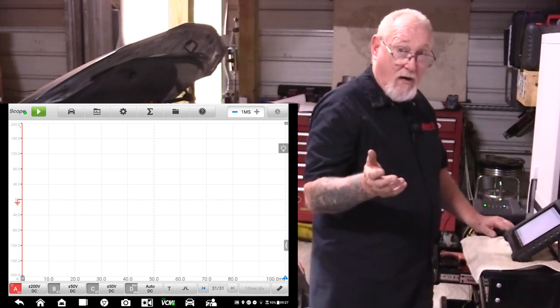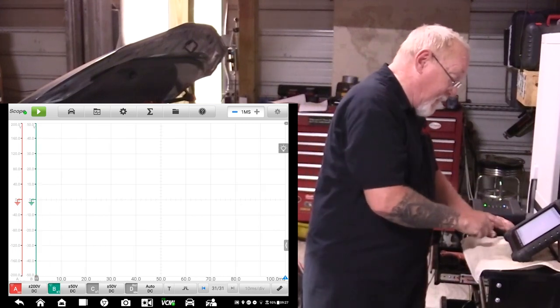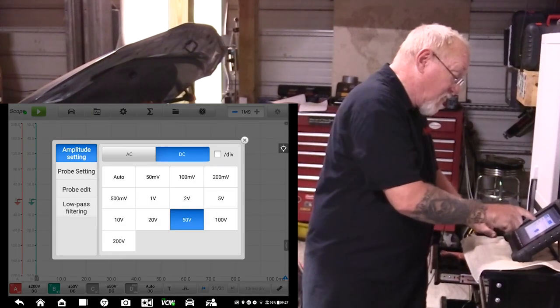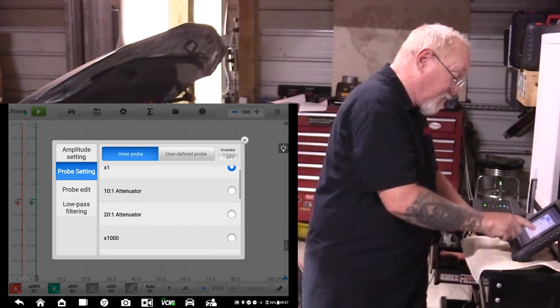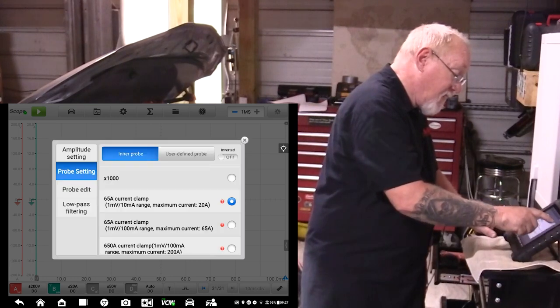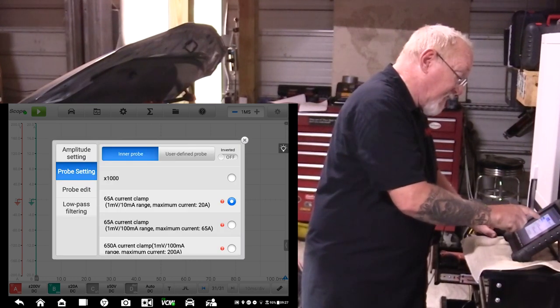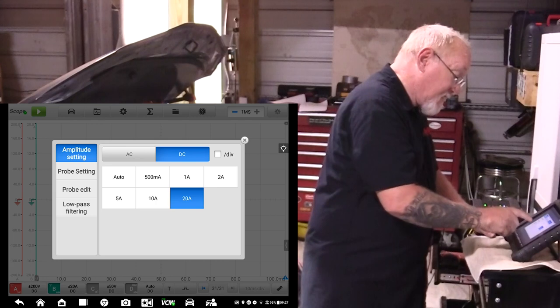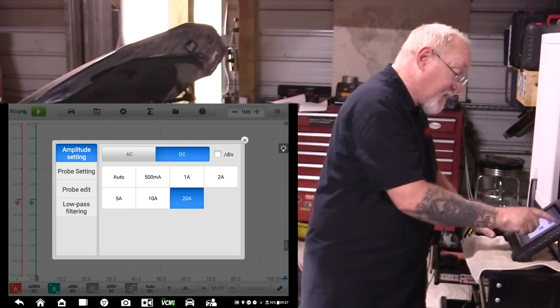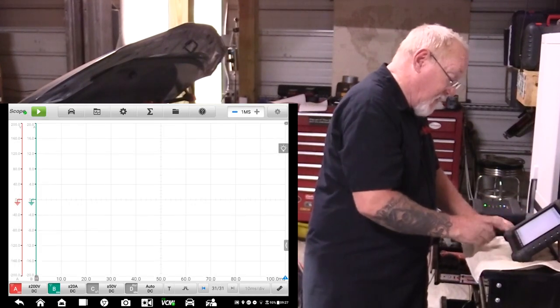We have the current clamp on channel B, so again we'll have to set that, pick the probe that we're using, and then we can set the scaling. We'll leave it on 20 amps for now; I can always change that.